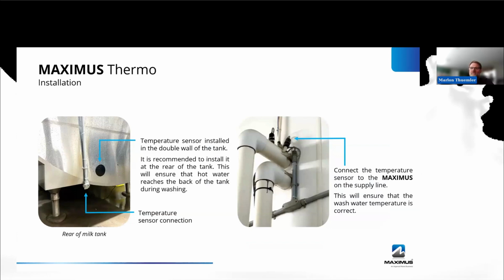Here's what you need to install a MAXIMUS Thermo system. This example refers to an installation with one tank and one pipeline. The MAXIMUS Thermo kit includes a MAXIMUS master, HMI, and the RTD module. Furthermore, you will require a milk tank sensor, a pipeline sensor, a 2-wire 18-gauge cable for the pipeline sensor, a 2-wire 18-gauge cable for the vacuum pump signal, a 4-wire 18-gauge cable for the communication wire from the master to the RTD module, a 10-wire 18-gauge wire for the milk tank sensor, and a 14-gauge 3-wire for the power supply to the MAXIMUS. A Cat 6 or higher is mandatory for the internet connection.